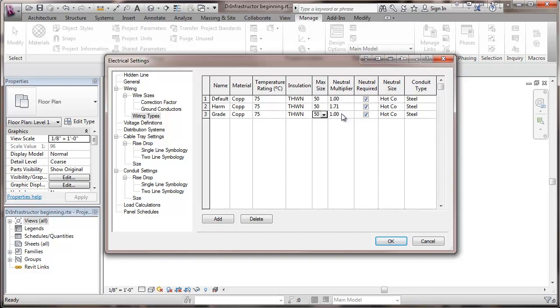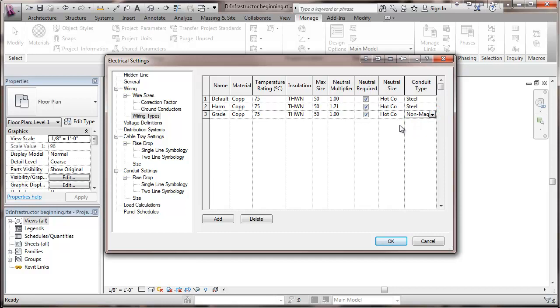Neutral multiplier being the same in this particular case. Also, the neutral, and my conduit type is going to be non-magnetic. I'll be running that in PVC.